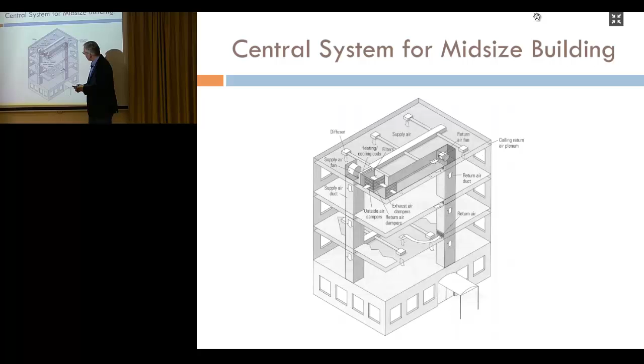Now these systems also vary the airflow, but there's one fundamental difference. Through the cooling coil here, you do not run water, but you run the refrigerant directly. These systems are called direct expansion systems. They take R134A or R410, these refrigerants, they expand in the cooling coil, and then a compressor condenses that, a compressor compresses it, a condenser condenses it, and rejects the heat. So in smaller or medium-sized buildings, we have a lot of direct expansion technology.